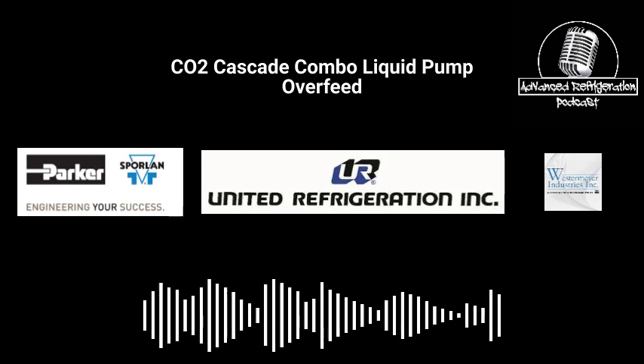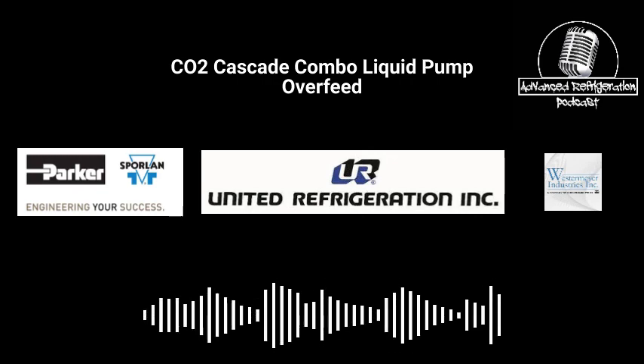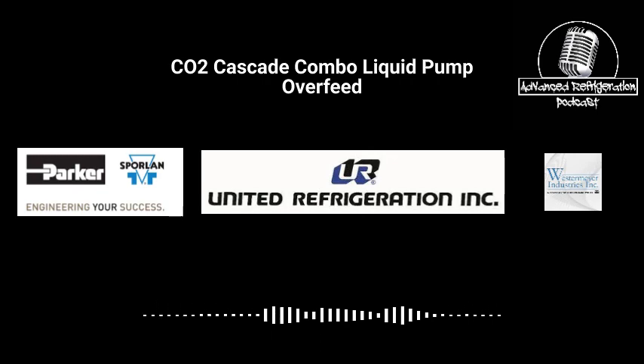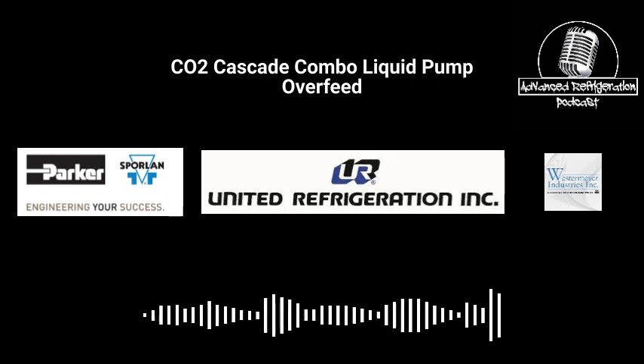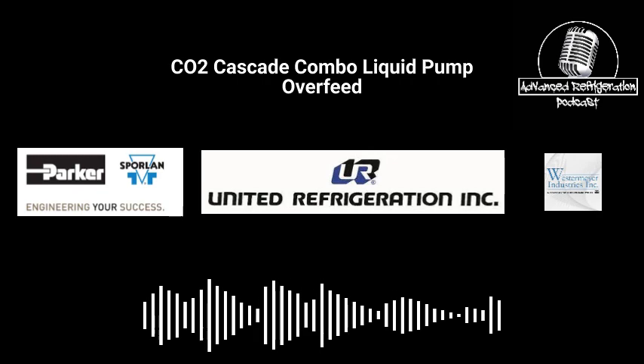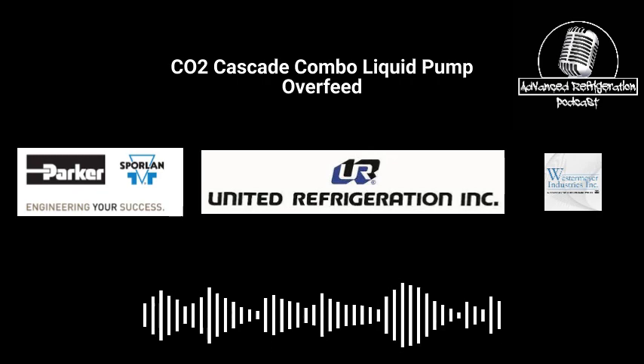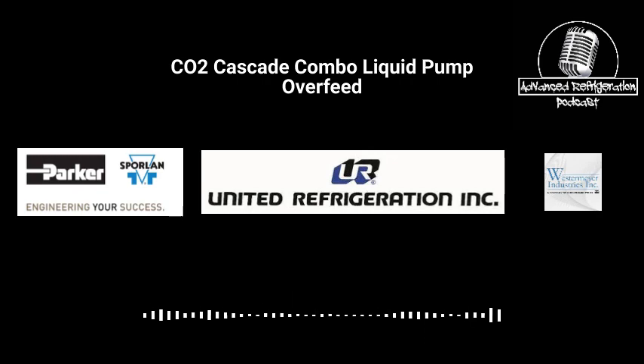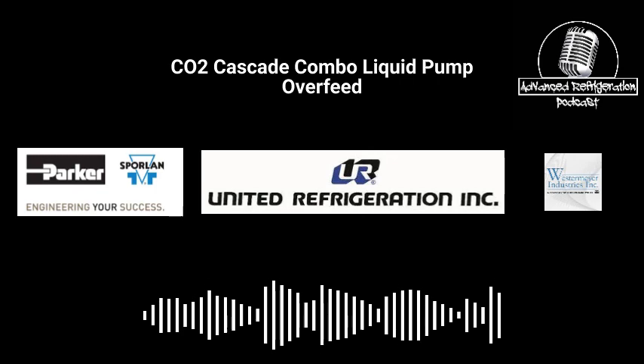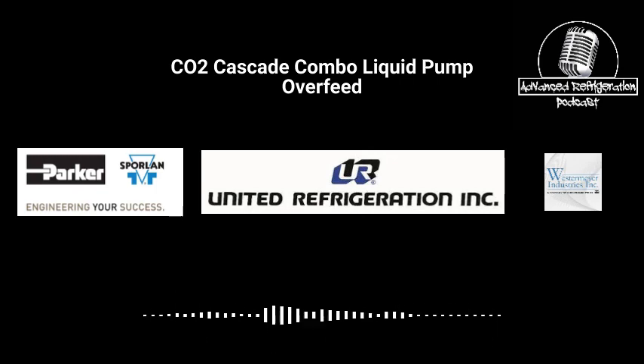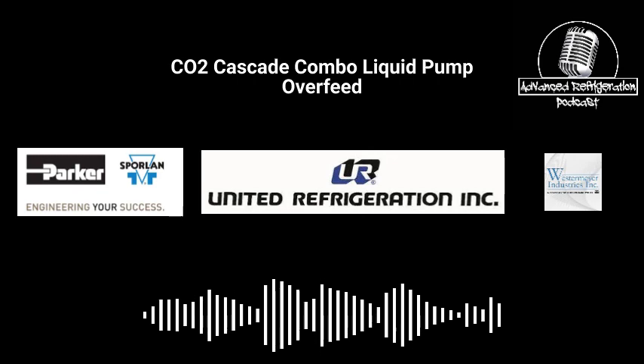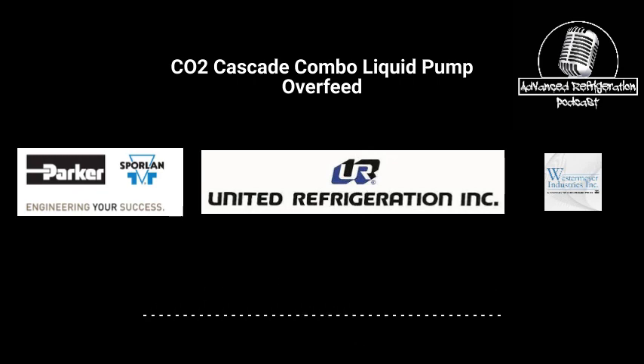Oh, so you're less likely to get the non-condensables, right? Oh, okay, I see what you're saying. Yeah, because you're pushing through it. It's not like the thermal siphon, where it's just working on that principle of cold attracting the CO2, attracting the vapor and dropping out liquid. Yeah, but in order to get those non-condensables, you'd still shut down the system, right? At least shut down the low temp stuff and then the medium temp stuff to basically get all that air to rise into those heat exchangers. The heat exchanger or the vessel is usually the highest spot. So it'd be no different than charging or purging a normal rack. Yeah, which you overdo. Gotcha.